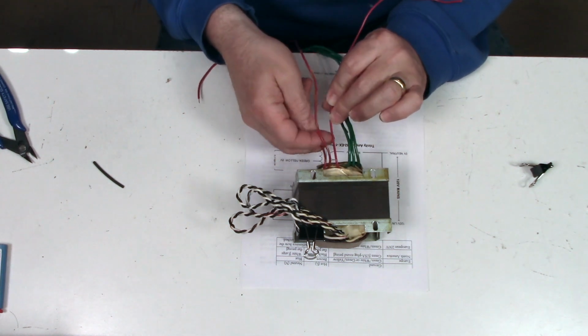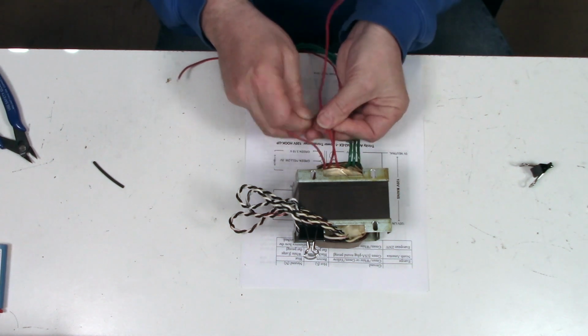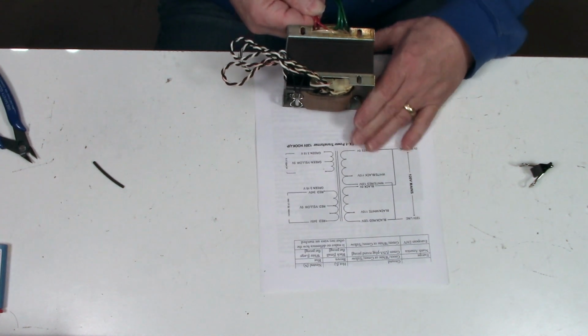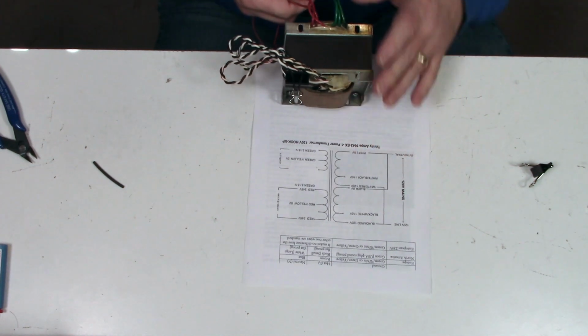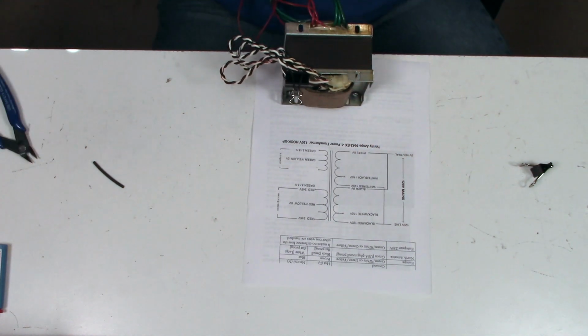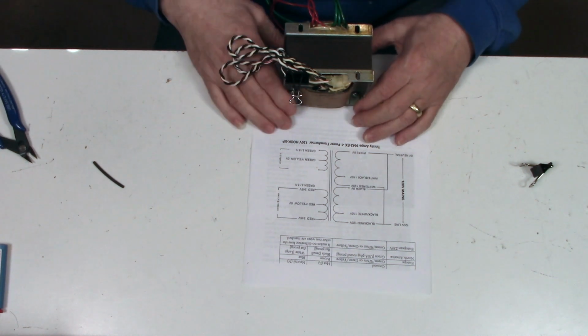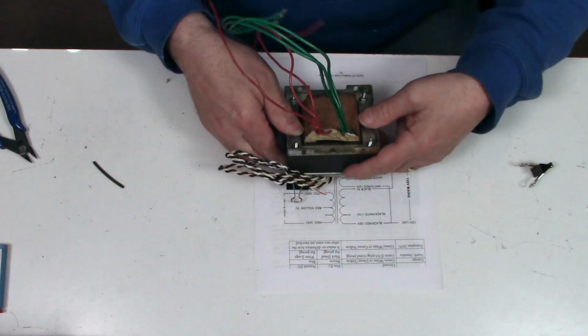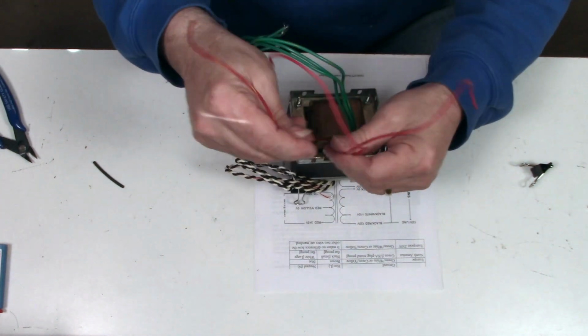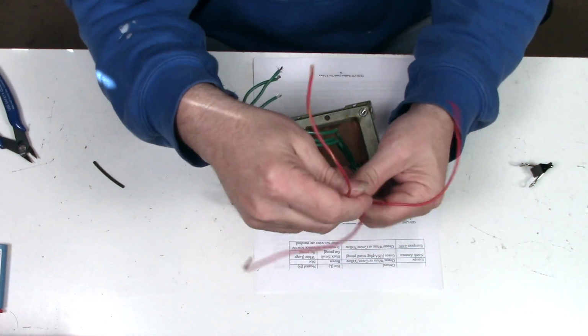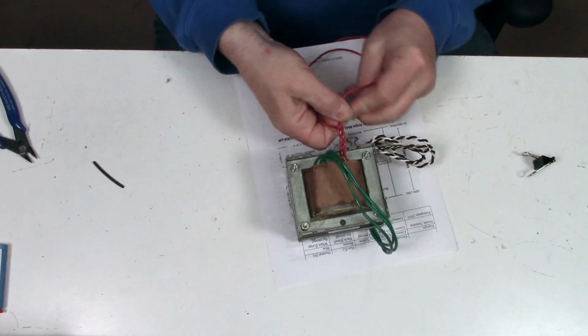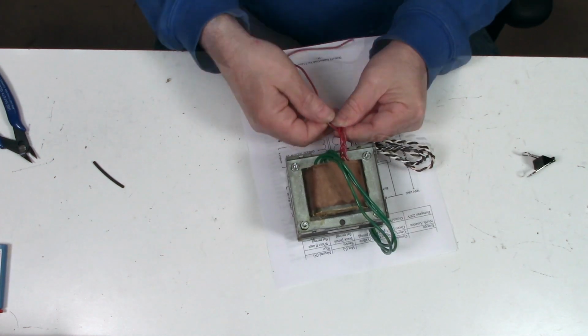So what we do with these is braid them. When you're trying to do this tightly, you can end up pulling on the transformer, and it ends up moving around a lot on you. One thing that can be helpful is to put it on its side and use the weight of the transformer against itself. Similar to twisting the wires, every few braids I'll give a little tug to tighten it and make sure everything's tightened up.